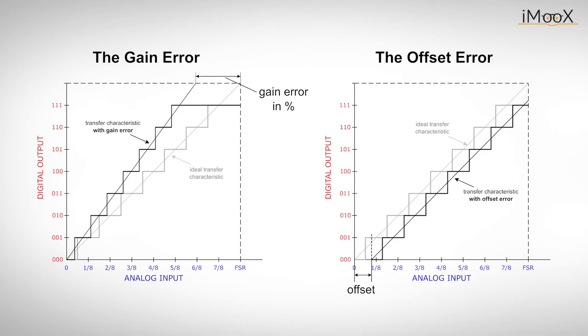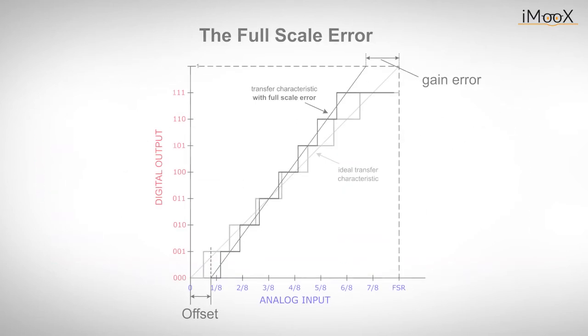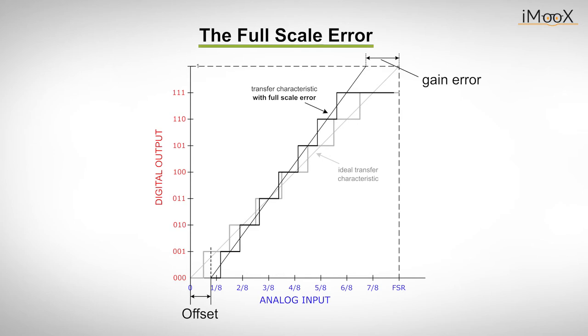Data sheets often also mention the full-scale error. The full-scale error simply equals the sum of the offset error and the gain error, as shown in this figure. Both gain and offset error are constant errors and can be eliminated by appropriate calibration.